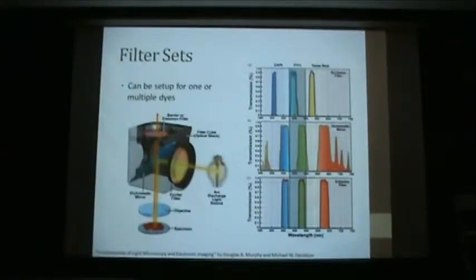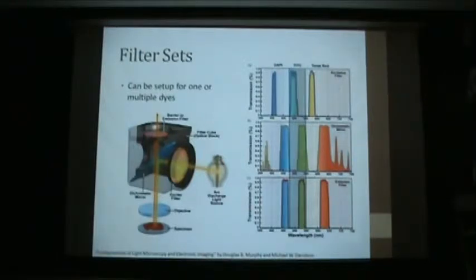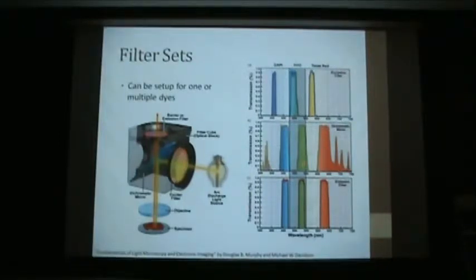The spectra on the side are for a filter cube that handles three different dyes. I've highlighted the FITC channel. Microscopists often use dyes as shortcut nomenclature — FITC, GFP, and Alexa 488 all have very similar spectral characteristics. So you'll come up to a microscope and someone will say 'this is the GFP filter,' and if you really have Alexa 488, you're in good shape. Here we're exciting FITC at 500 nm; the dichroic mirror reflects light at 500 but transmits longer wavelengths, and then the emission filter transmits 510 to 540 nanometers.